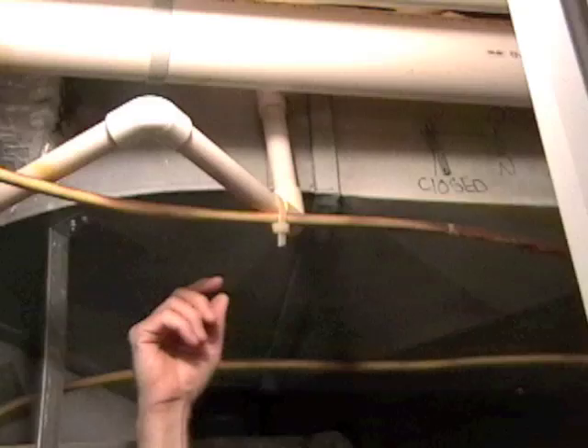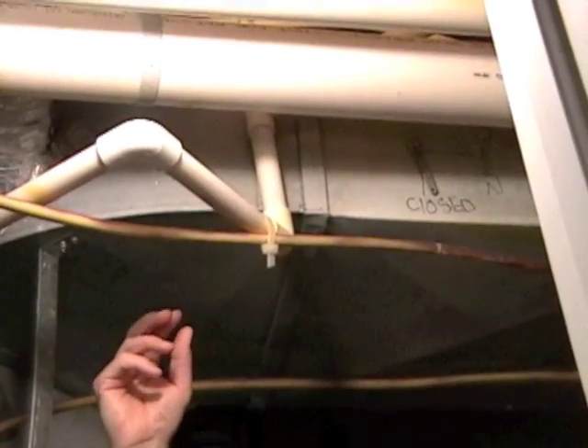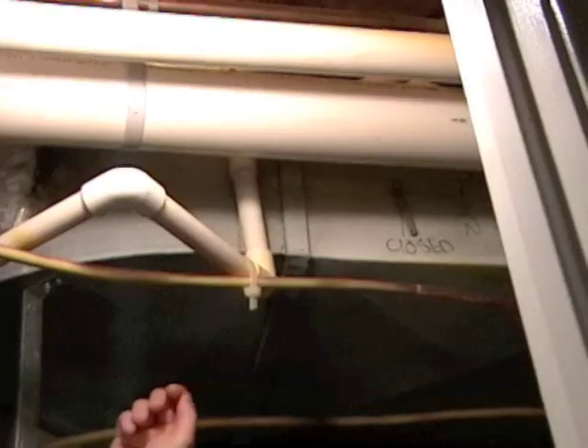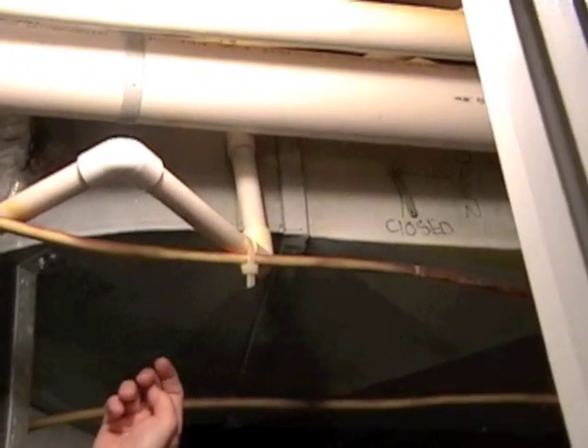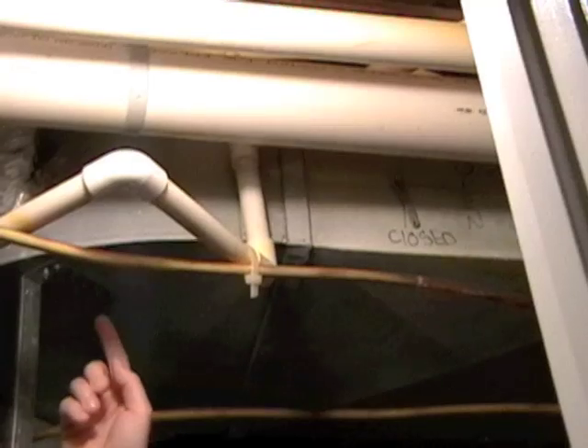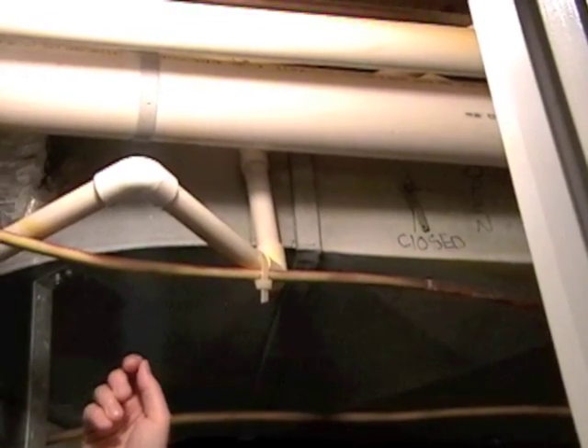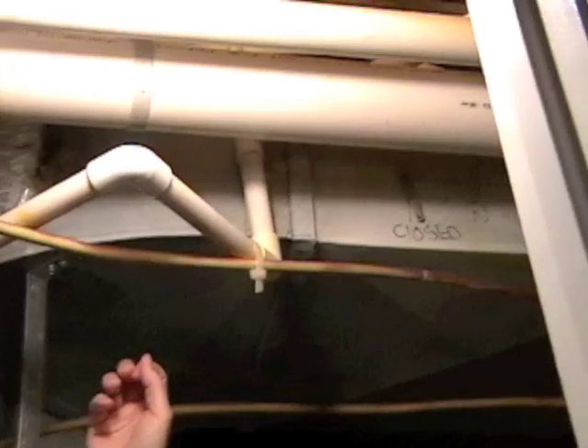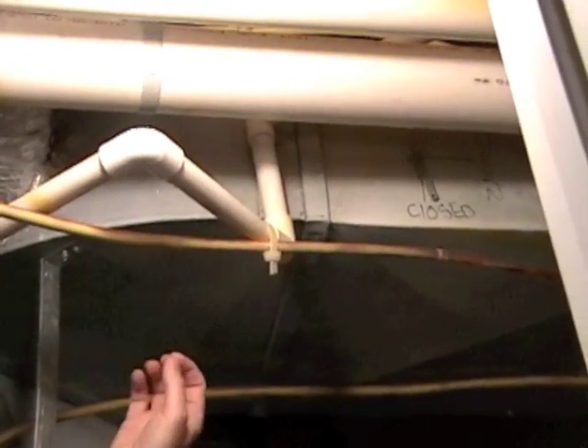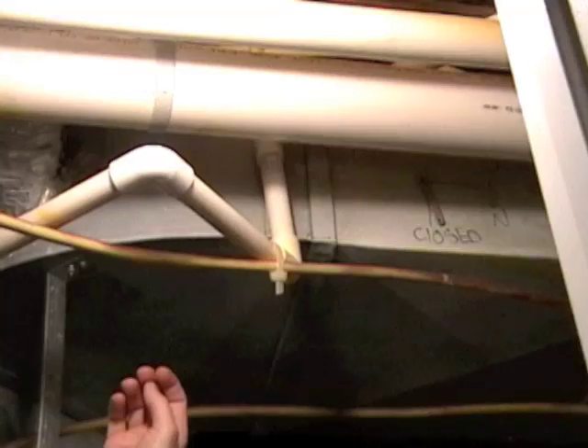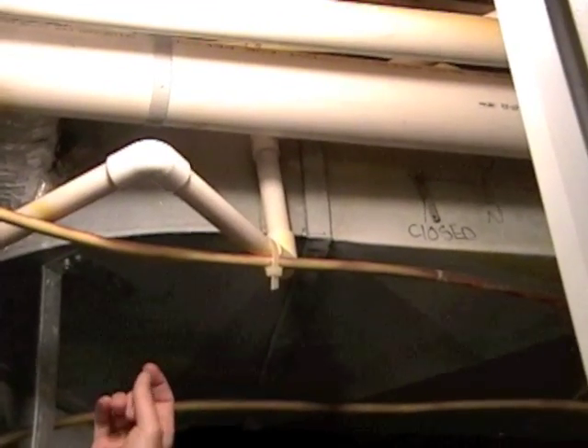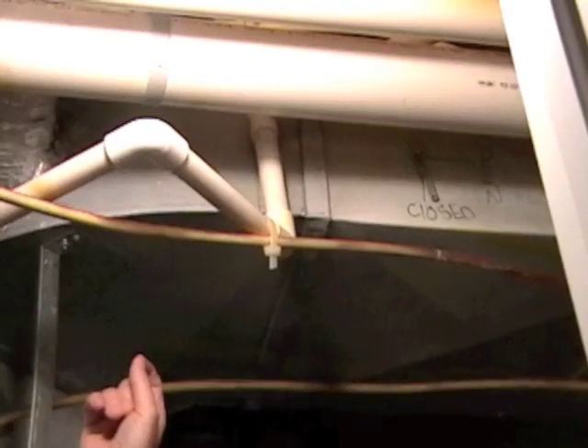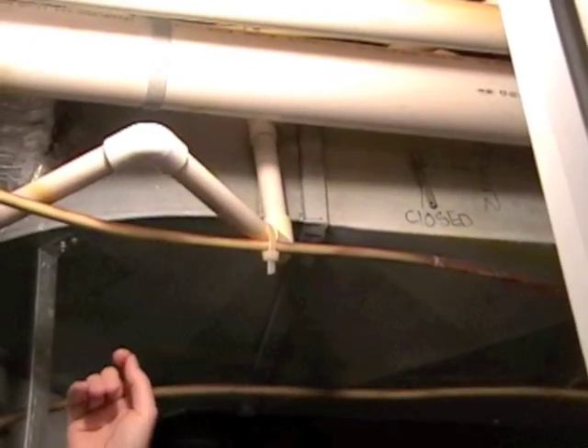This process works the best if you can get a partner with a cell phone to call you as you adjust the dampers and at the same time adjust the room registers. As logic would have it, in summer you should wish to have more air on the top floor, moderate air on the main level, and very little AC or cold air on the lower basement area. That's it.